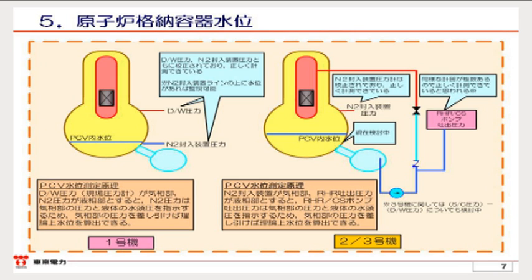In addition, Units 2 and 3 have similar measurement basics. They have pressure from the nitrogen supply apparatus as illustrated in red, and another one from the hydraulic head pressure of the suppression chambers, as the pumps in relation to the discharge pressure indicator, whose water comes from these suppression chambers in the residual heat removal system, do not basically work currently. Therefore, we think we can also estimate the water levels of the primary containment vessels if we subtract the instrument reading of the discharge pressure of the pumps in the residual heat removal system from that of the nitrogen supply apparatus. We have slightly different approaches to each of the units, 1 to 3, but have been currently considering methods to theoretically calculate water levels in the primary containment vessels and will continue to work on this.